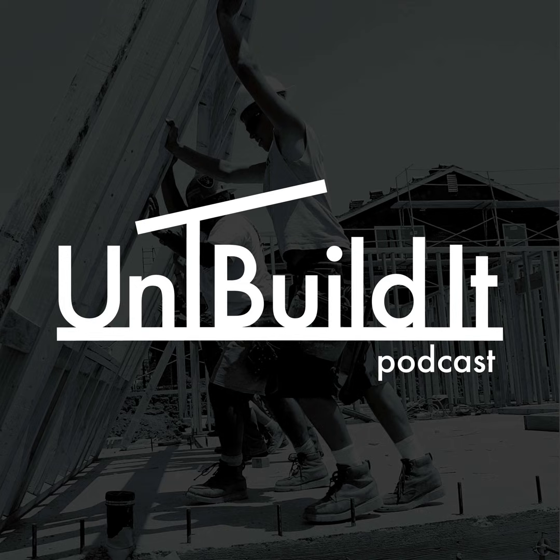We kind of glazed over. You were starting to say the difference between HRV and ERV, and we just talked about HRV. So ERV, there's another load that's taken care of there, and it's the moisture. Right. The only thing the ERV can do is it helps to maintain the difference between the two streams. It can't actively move moisture from one stream to the other, but it can help to reduce how much it would dehumidify in the winter or how much it would increase the humidity in the summer. But it can't actually dehumidify. By trying to equalize. Yeah. By enthalpy. Yeah. Enthalpy is actually capturing both the latent and the sensible load in the exchange.